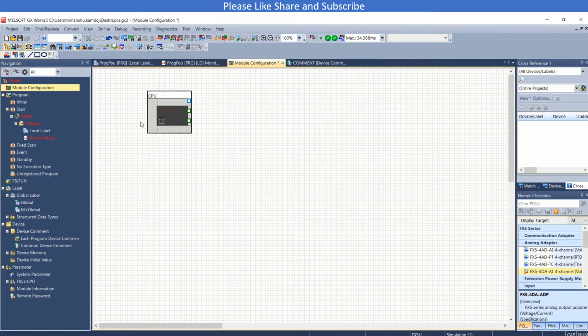In today's video we will learn how to use the FX5-4DA-ADP card. So let me just drag and drop it from this element selection here. I'll drag and drop it in this section. You can use up to 4 cards for analog here, and if you are using a communication card then maximum up to 2. So here I have used only one ADP card.